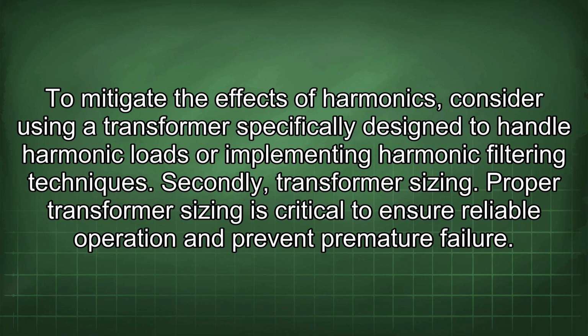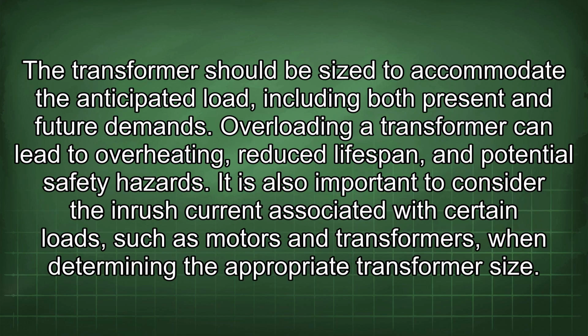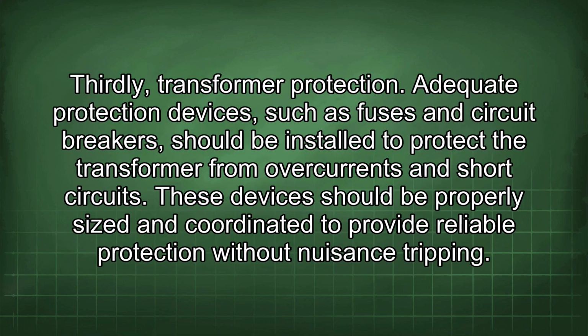Secondly, transformer sizing. Proper transformer sizing is critical to ensure reliable operation and prevent premature failure. The transformer should be sized to accommodate the anticipated load, including both present and future demands. Overloading a transformer can lead to overheating, reduced lifespan, and potential safety hazards. It is also important to consider the inrush current associated with certain loads, such as motors and transformers, when determining the appropriate transformer size.